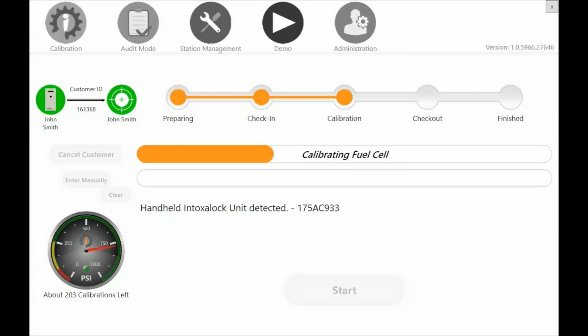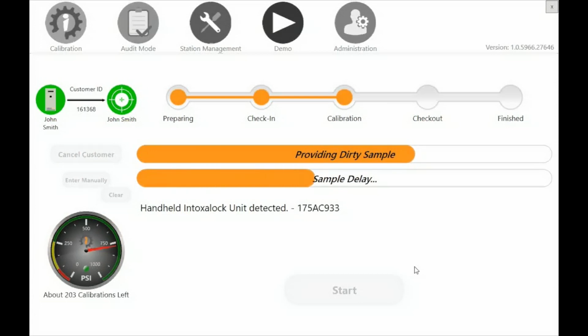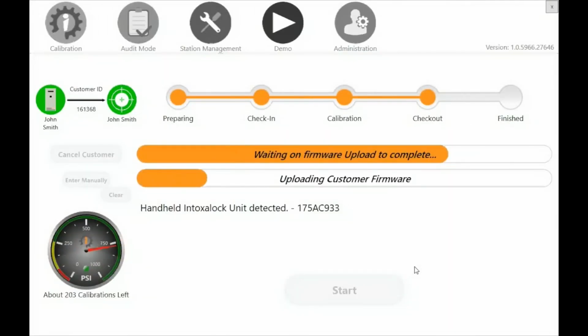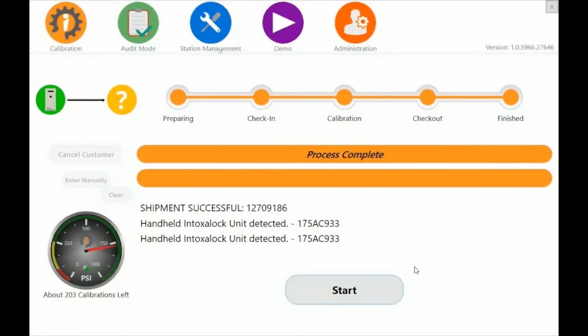The station will apply all necessary gas samples. Once the station has applied the necessary samples, it will load the state-specific firmware for the customer. Once the calibration is complete, you will see Shipment Successful and a transaction number right below the Process Complete bar. It will also show you which handheld you started with and which handheld you finished with for calibration.